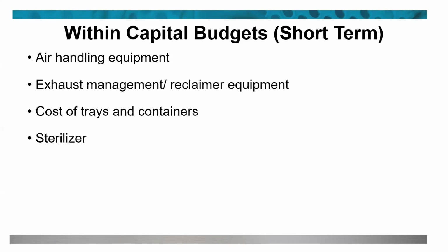Some other things that you may want to consider too is, do you need to have a certain kind of trays? Like I said, they should be approved for vaporized hydrogen peroxide. Your wrap should be approved for vaporized hydrogen peroxide. And the connectors, if you're doing any kind of device connectors for your endoscopes, those will need to be considered too.